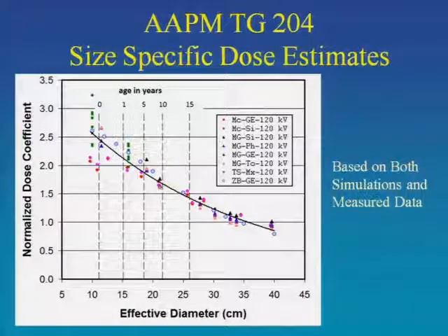But you can see what happens. If you have small patients, you've got to multiply by a number. And peds patients, and by the way, this particular chart is based on the 32 centimeter phantom. And yes, some scanners report CTDI to pediatric abdomens on 32 centimeter phantoms. So we have this table. We also have another table in the report where it's based on 16 centimeter phantoms because some manufacturers report on 16. Okay, someday we'll get that sorted out, but not just yet.